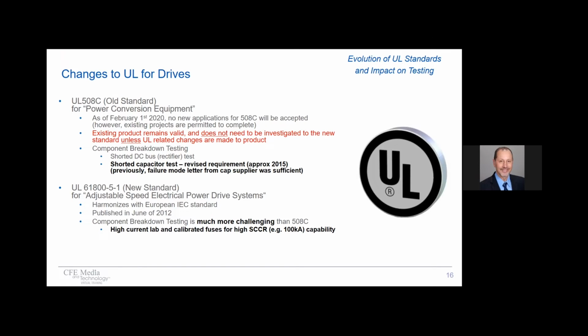And not only did that testing become more severe under 508C, it's become even much more challenging under the new standard, in the fact that to attain the high withstand ratings, such as 100,000 amps, drive manufacturers actually have to do that now in a high current lab with calibrated fuses. So it definitely has gotten more challenging to do.